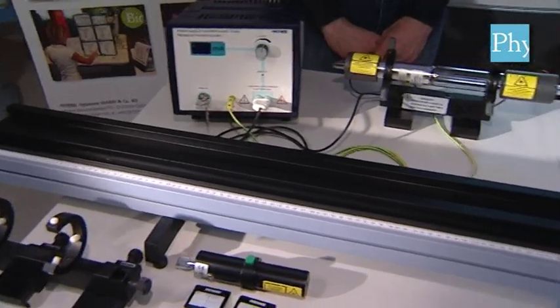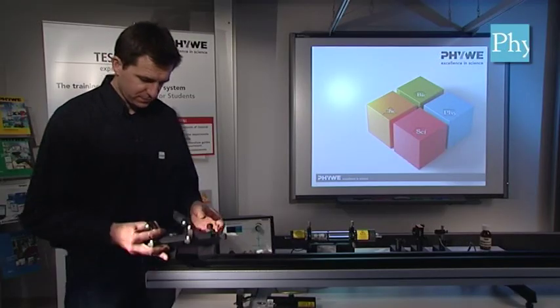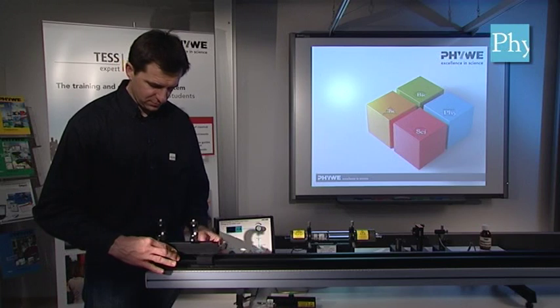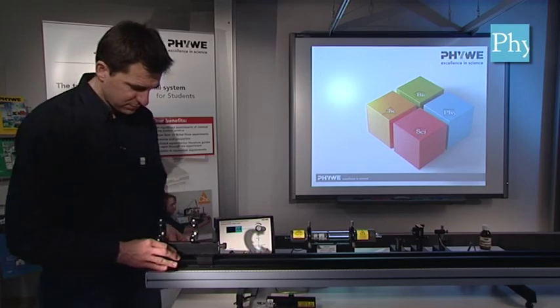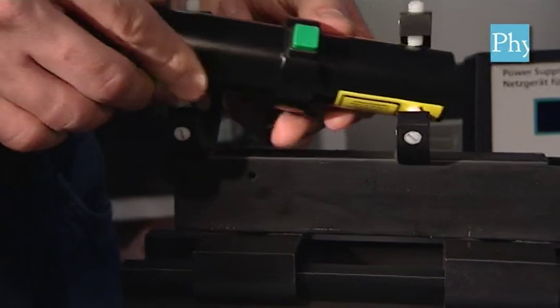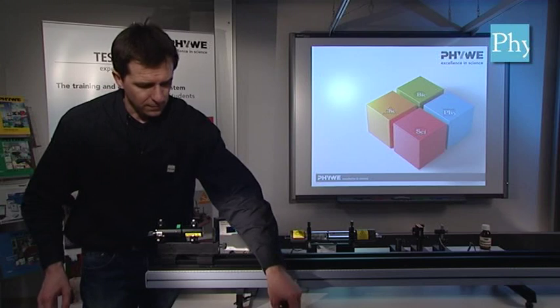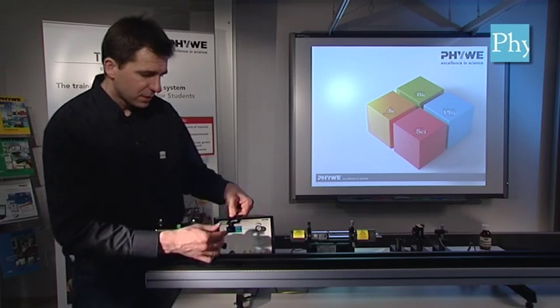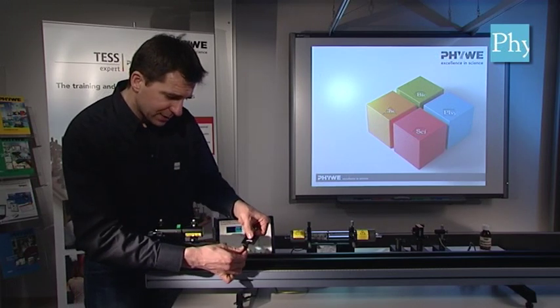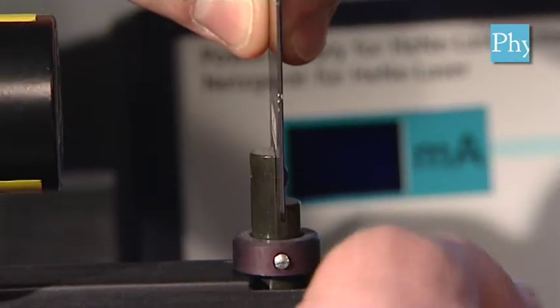Starting with the empty optical bench we will first mount the alignment laser on the left side of this bench. We also mount the diaphragms that are pre-adjusted here at PHYWE. The one labelled left diaphragm goes directly in front of the alignment laser, with the label pointing direction to the laser.